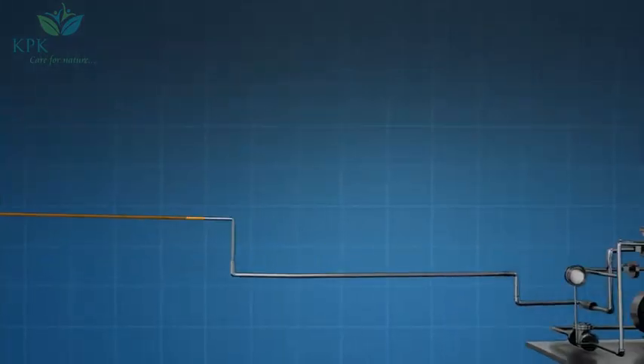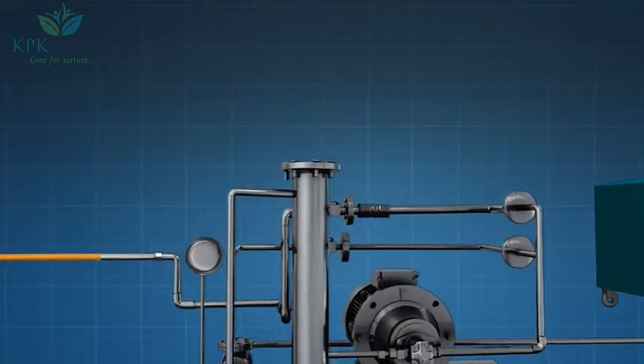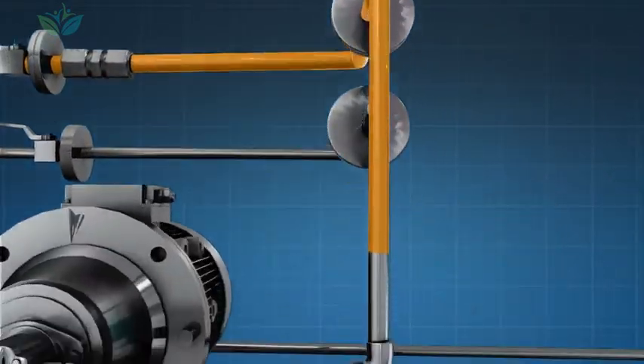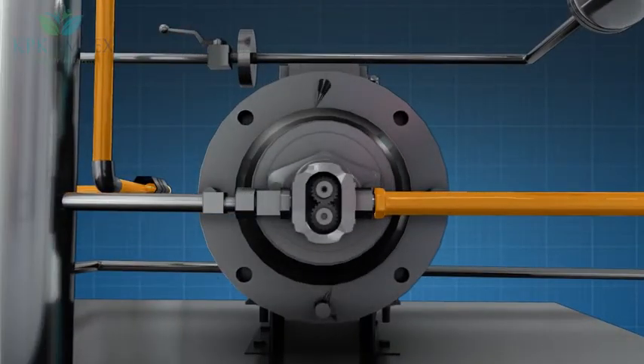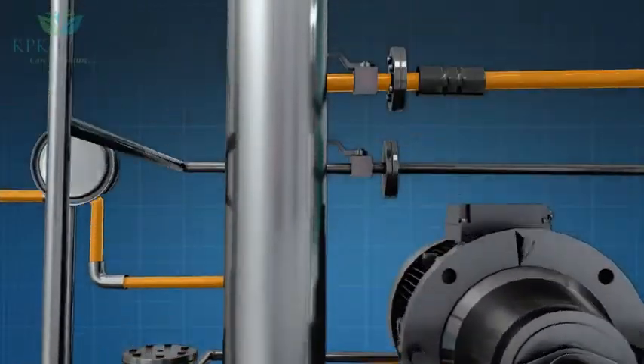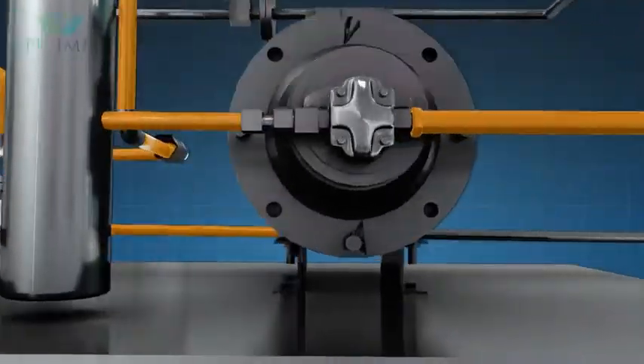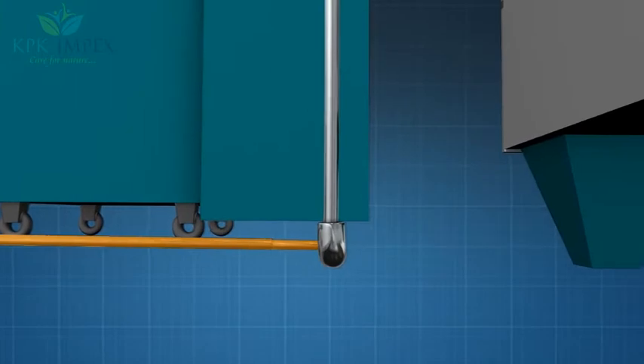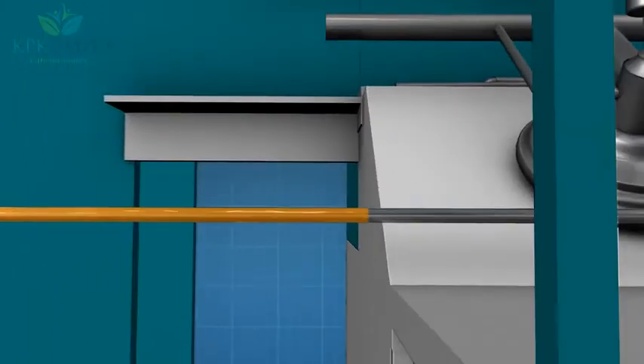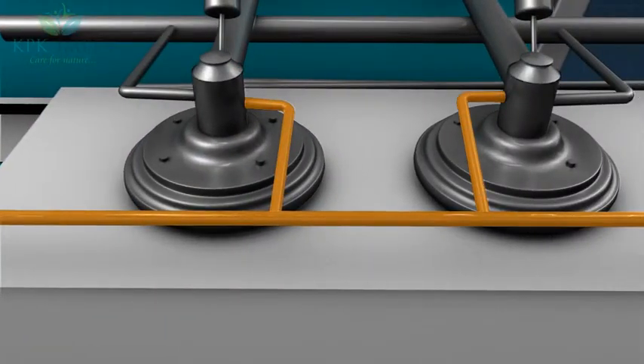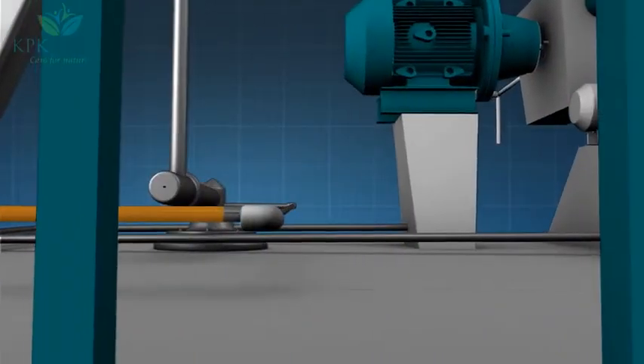Normal setup of melting furnace fired by furnace oil consists of service a day tank, heating and pumping unit with pre-filters, gear pump for increasing the fuel pressure from atmospheric pressure to 1.5 bars, a line heater to increase fuel temperature up to 75 degrees Celsius. Combustion takes place at burner where air and fuel line are connected.